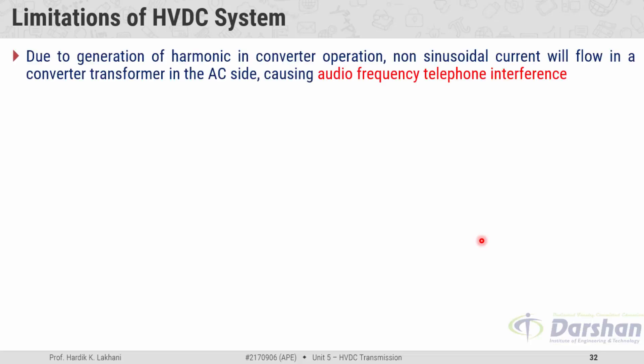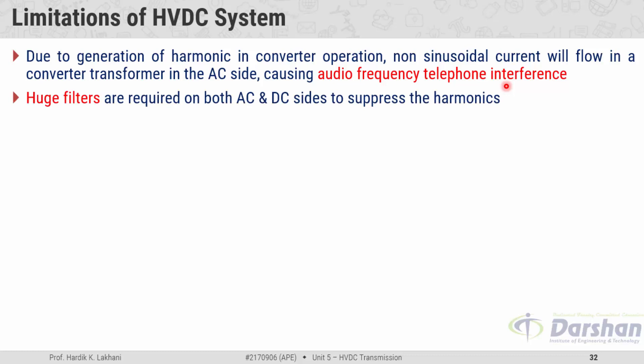Limitations of HVDC systems: Due to generation of harmonics in converter operation at the sending-end rectifier and receiving-end inverter, non-sinusoidal current flows in the converter transformer on the AC side, causing audio frequency telephone interference. Filters are required on both AC and DC sides to suppress harmonics — AC filters are connected to the AC bus and DC filters are placed after the smoothing reactor to eliminate higher order harmonics.